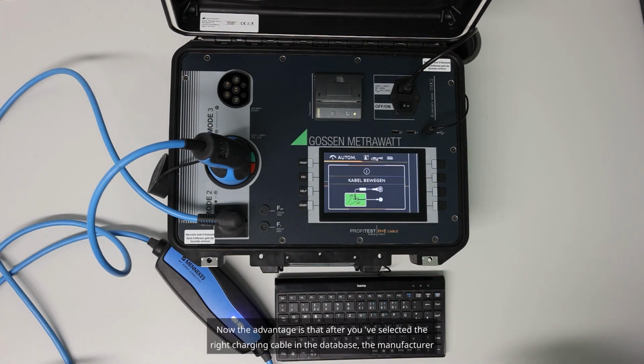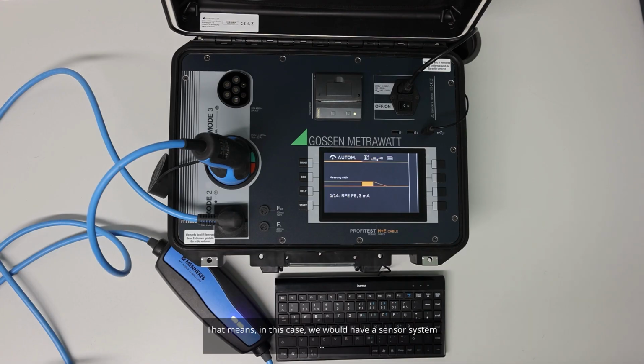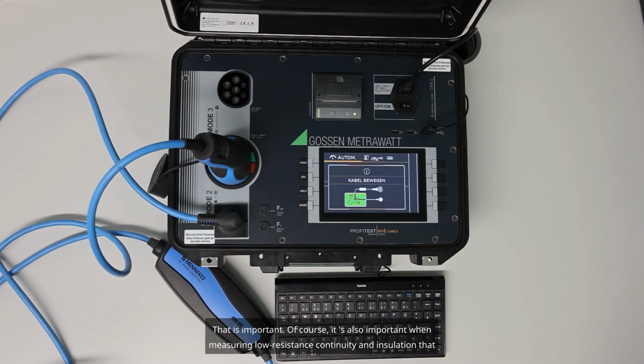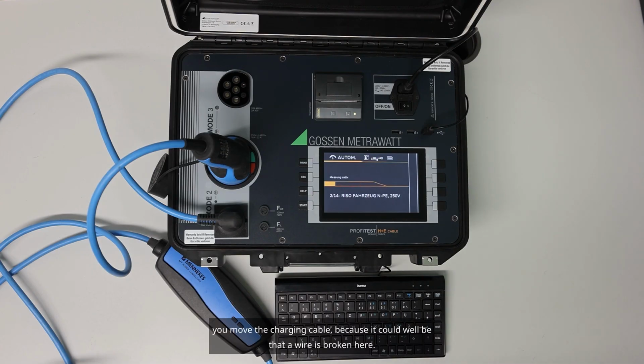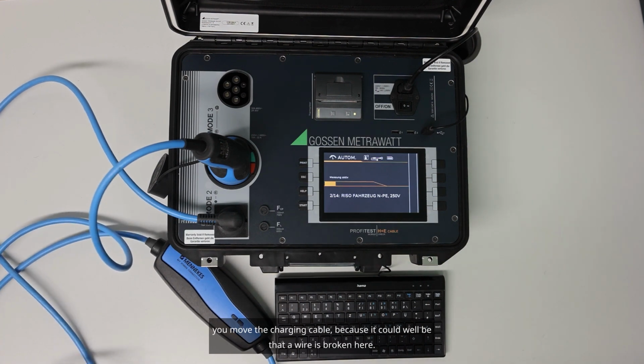Now the advantage is that after you've selected the right charging cable in the database, the manufacturer data is stored for you. That means in this case, we would have a sensor system, 6 milliamps, we have a switching protective earth, so there's the possibility to measure here with 3 milliamps. This is automatically specified for the charging cable. That is important. Of course, it's also important when measuring low resistance continuity and insulation that you move the charging cable, because it could well be that a wire is broken here.